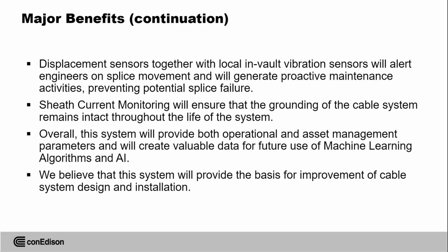Displacement sensors, together with local vibration sensors, will alert engineers to splice movement and will generate proactive maintenance activity, preventing potential splice failure. Shield current monitoring will ensure that the grounding of the cable system remains intact throughout the life of the system. Overall, this system will provide both operational and asset management parameters and will create valuable data for future use of machine learning algorithms and artificial intelligence. And we believe that the system will provide the basis for improvement of the cable system design and installation.